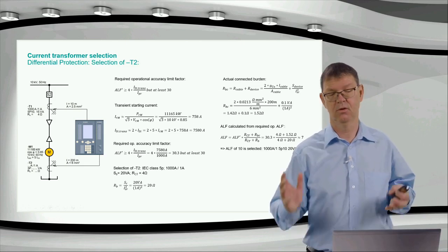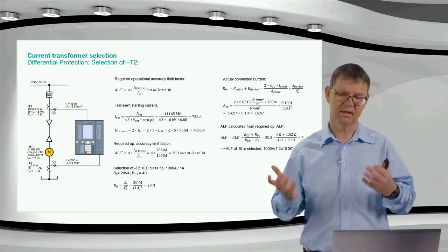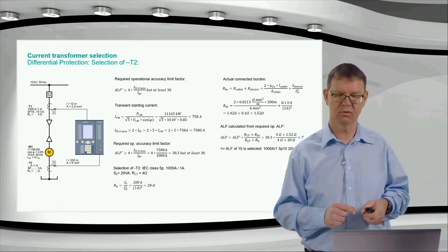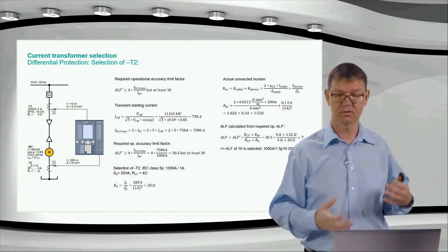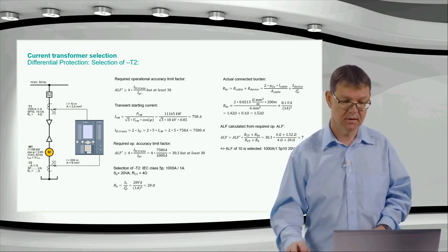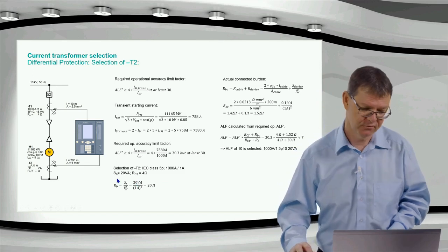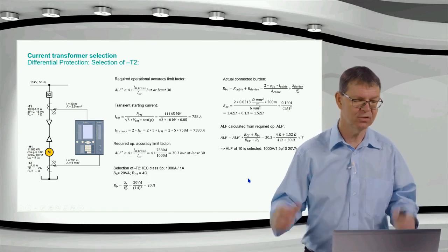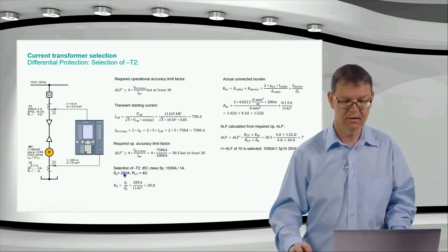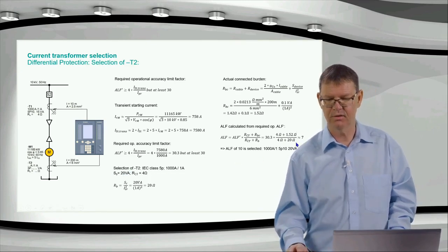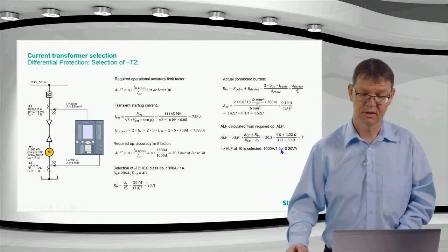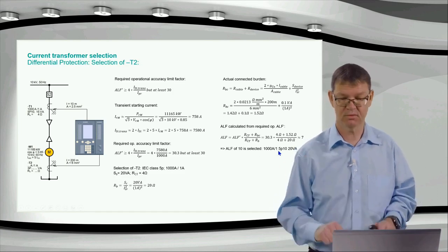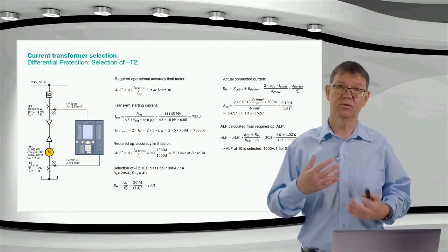So in that case, I could say, okay, instead of 7, I put a little bit of margin on top of this, so 10 would be good. So I would then select a 1000 to 1 amp, 5P10, and then the 20 VA fits quite well. What we need to say for that is I could go here also with 10 VA, but then I get a higher value here at the end. And then I need to select instead of 5P10, maybe a 5P15 or 5P20.